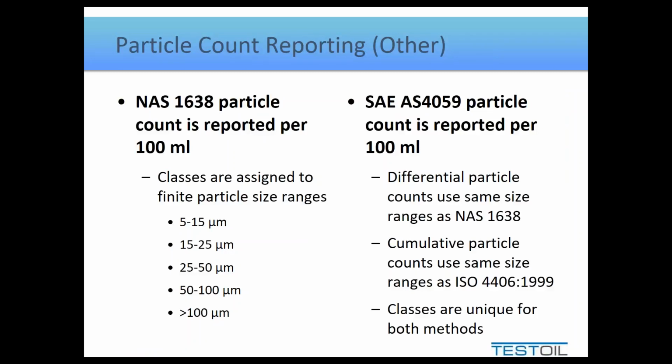One is called NAS 1638. It is rather archaic and hasn't been considered proper to use on any new pieces of equipment, but again, industry has many older pieces of equipment that when they were built, this was the de facto standard. So you may still see this in literature or within your own specifications.